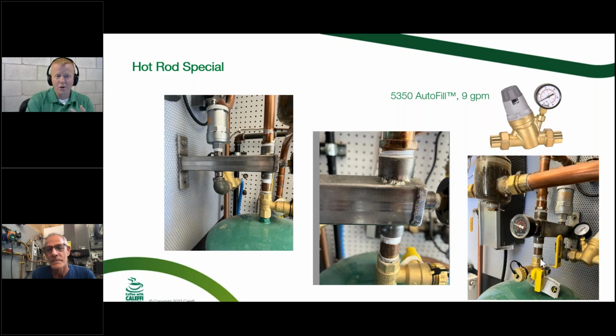You need to get the water pressure out of it in order to test the air side or change it for whatever reason. But another little trick that I learned just over the years is, if it is waterlogged and you don't want to deal with the bear hug shower and everything like that, just run a zip screw in there and then pull that zip screw out and have that water shoot out in whatever direction you want. Put a new tank in there and you're off and running. So yeah, zip screw is a nice way to go.